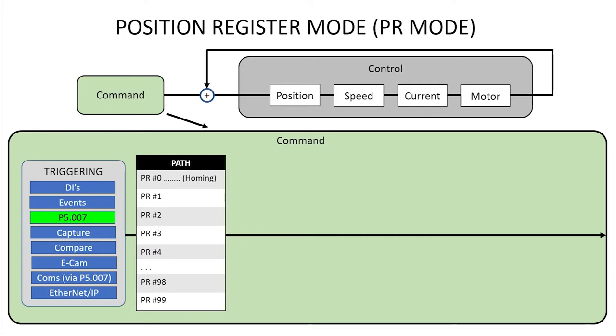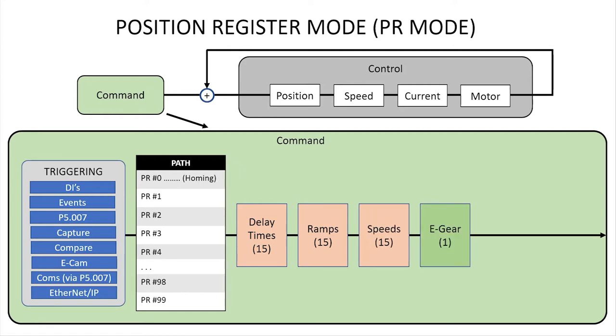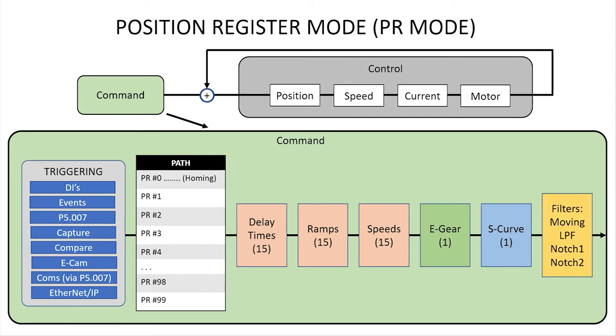Each of these can use any of 15 possible delays, acceleration and deceleration ramps and speeds. You can also setup electronic gearing and apply an S-curve to smooth transitions between the speeds and various kinds of filtering.